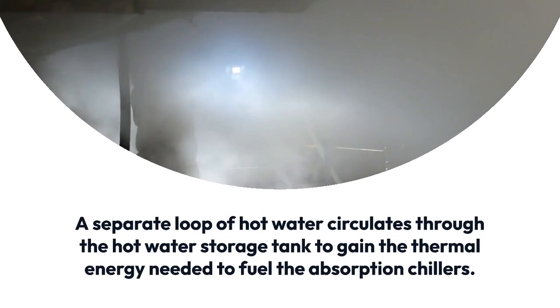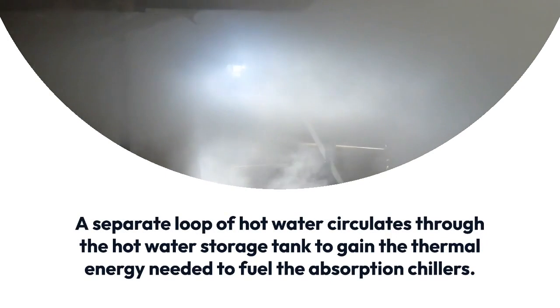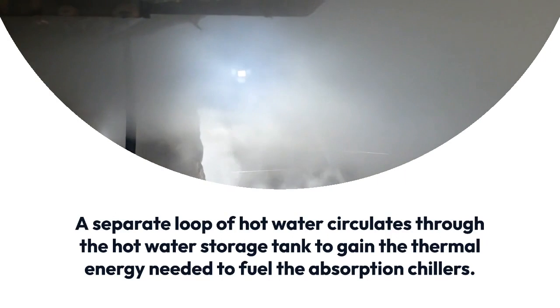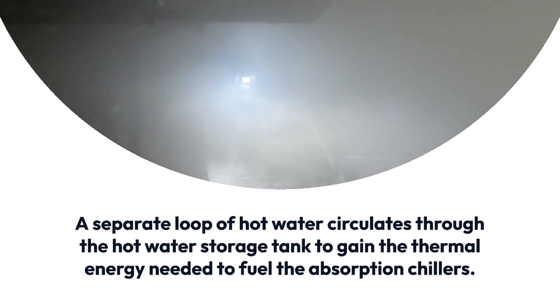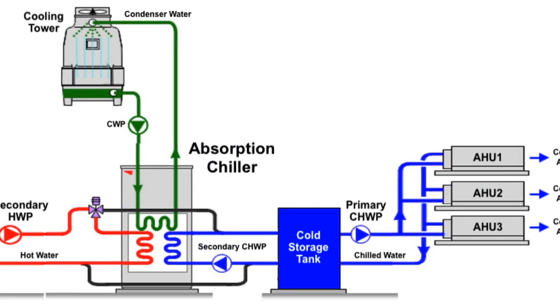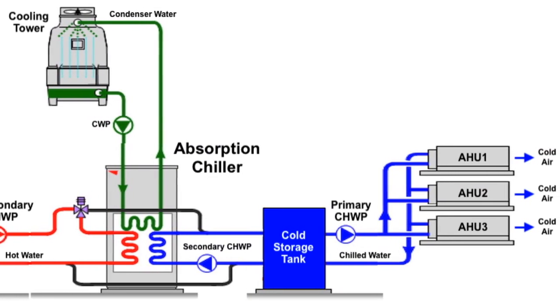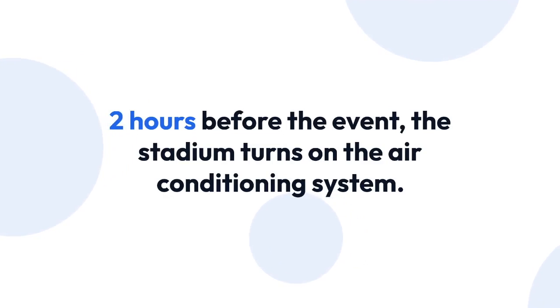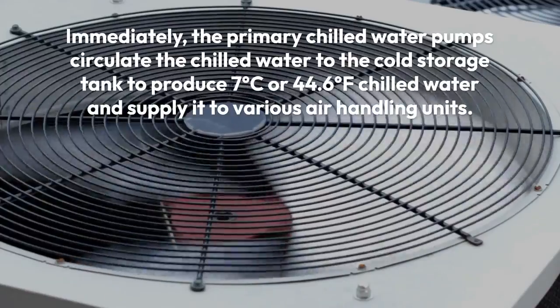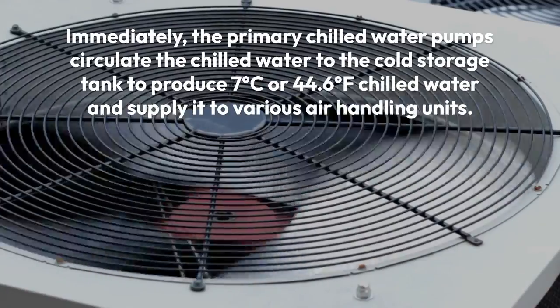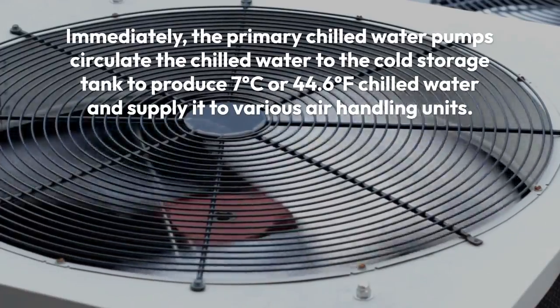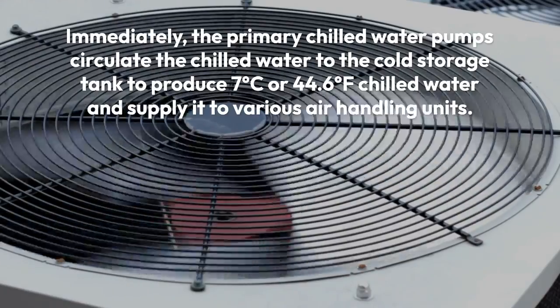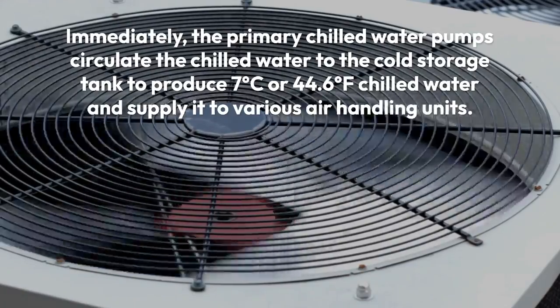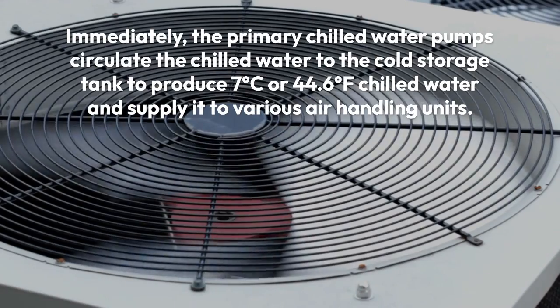A separate loop of hot water circulates through the hot water storage tank to gain the thermal energy needed to fuel the absorption chillers. Through the absorption chiller cooling process, cold water is produced and then stored in a cold storage tank. 2 hours before the event, the stadium turns on the air conditioning system. Immediately, the primary chilled water pumps circulate the chilled water to the cold storage tank to produce 7 degrees centigrade or 44.6 degrees Fahrenheit chilled water and supply it to various air handling units.